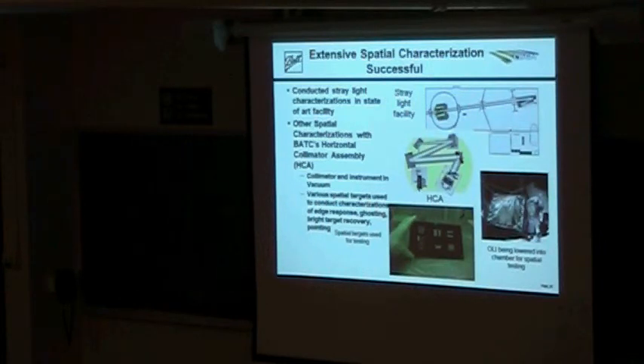Additionally, we also had to measure how sharp a response this thing had to edges on the ground. MTF, modulation transfer function, is one measure of that, which you may be familiar with. Our requirement was in terms of what we called an edge slope response. In other words, how sharp is an edge target actually imaged inside the instrument. And it's a ratio, typically. If you look at a very sharp edge, for example, here, in reality that's sharp up in the projector, but on the screen it's not that sharp. It actually blurs out, okay? And so that's the type of thing you're measuring for an instrument like this, because you want to make sure that you have a very tight sampling of the piece on the ground that you're trying to measure in order to get the appropriate accurate response for monitoring these things over time.